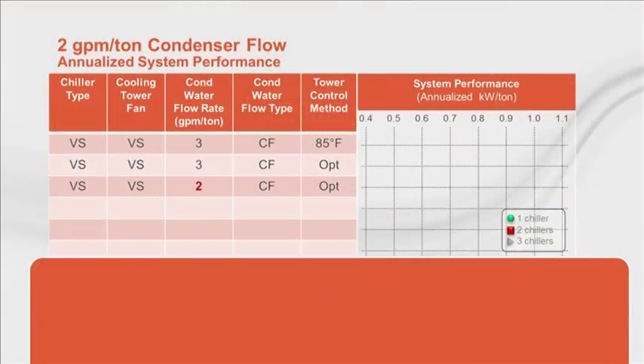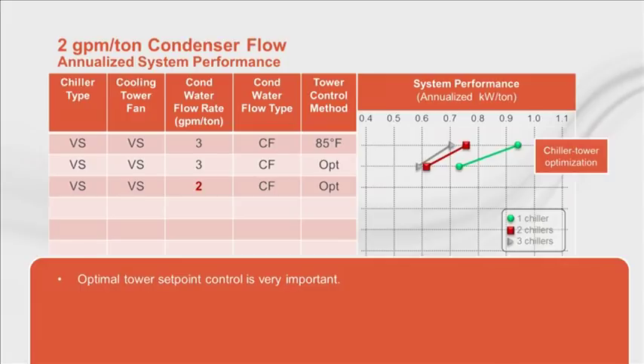Our base case uses a fixed 85-degree tower set point. This happens more often than most people believe because the system was commissioned with the design day in mind and to make sure the chillers are capable of working on the hottest day of the year. But on all those other days, we can optimize our cooling tower fan control and use the drive to slow down the tower fans. Note the huge change from improper tower fan control, no matter how many chillers we have.